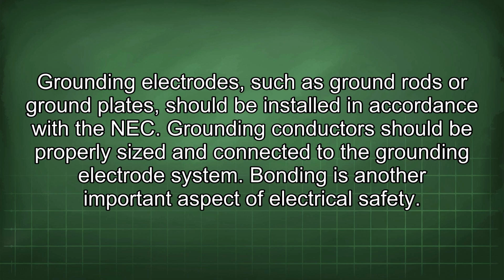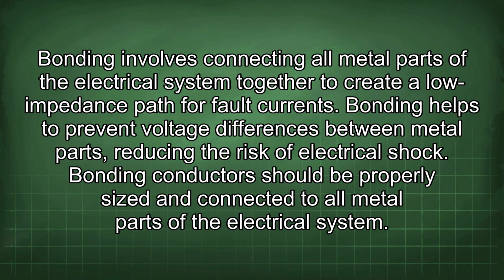Bonding is another important aspect of electrical safety. Bonding involves connecting all metal parts of the electrical system together to create a low impedance path for fault currents. Bonding helps to prevent voltage differences between metal parts, reducing the risk of electrical shock. Bonding conductors should be properly sized and connected to all metal parts of the electrical system.